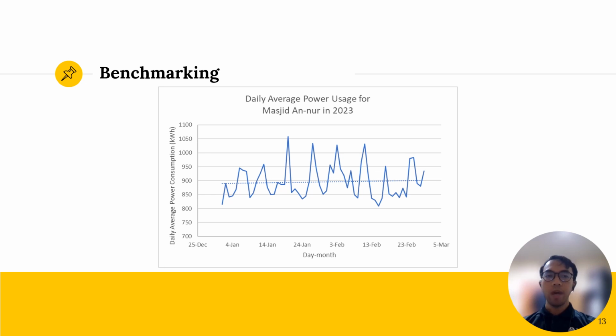We also received the DPM for An-Nur Mosque from the person in charge of the mosque. We extracted the data for 2 months, January and February of 2023. There are consistent peaks in power consumption of around 1000 kilowatt hour every Friday due to Friday prayers. But the average daily power consumption is just around 895 kilowatt hour, as shown from the straight dotted line on the graph. Comparing the average daily power consumption obtained from the DPM with the calculated daily power consumption, which is around 697 kilowatt hour, there is a percentage difference of around 20%. This is because of the non-uniform daily power usage of the building.